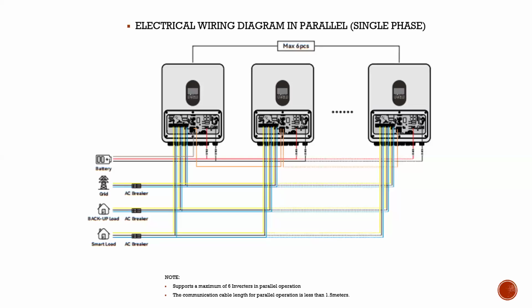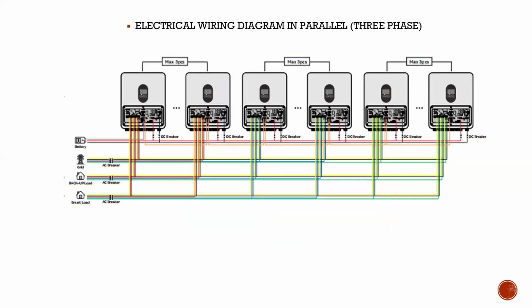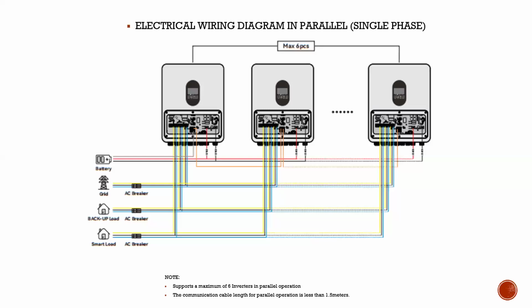And then of course, the next slide is the electrical wiring diagram for a parallel system. So of course, you're paralleling your system. You should parallel your load 1 together. You parallel your grid input together. And of course, you parallel your battery bank also together. Let me quickly say this. Our paralleling is one of the easiest paralleling systems you're going to see in the market because it does not stress you at all. All you need is just a communication cable, no load synchronizing cable, no current sharing cable, just a normal single cable. Any RJ45 cable would work.